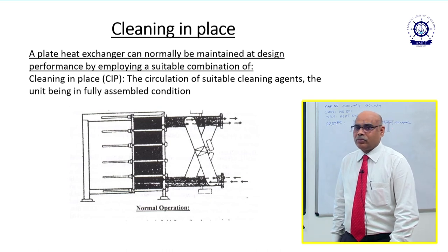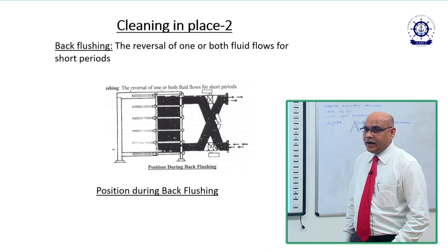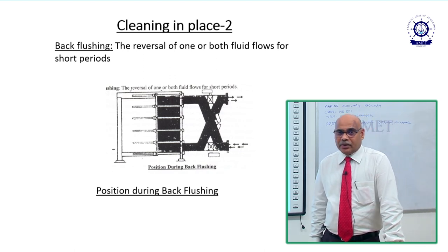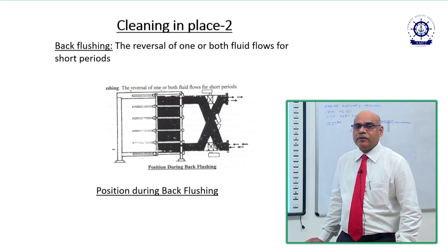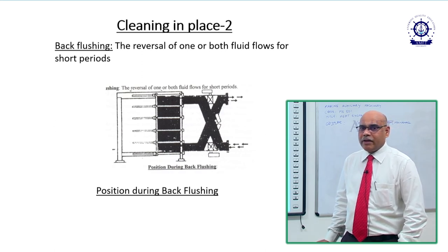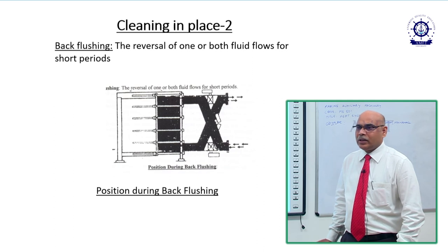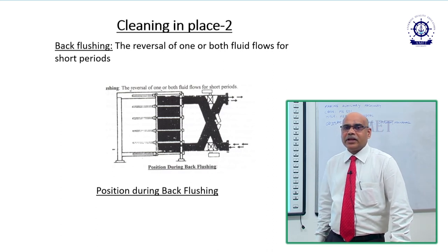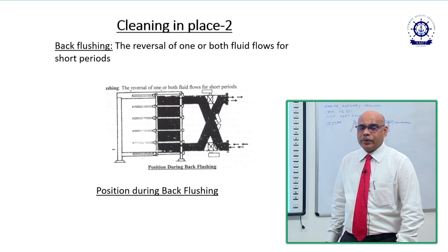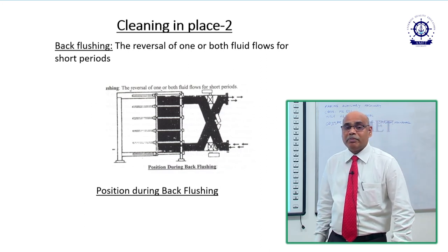Chemical cleaning in place is the most modern method for cleaning plate type heat exchangers. Back flushing is another option — one of the fluids flows in the reverse direction. For example, seawater is diverted to flow in the reverse direction. This removes all debris and clogging from the plates and improves the performance of the heat exchanger. At regular intervals, plate type heat exchangers should be back flushed.